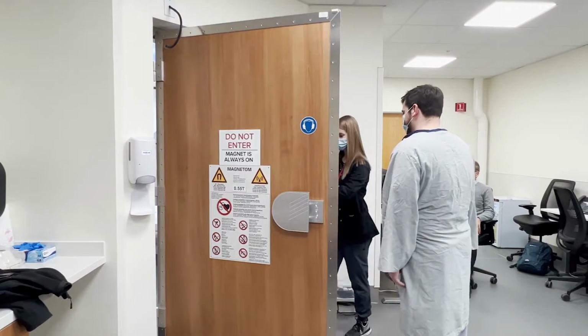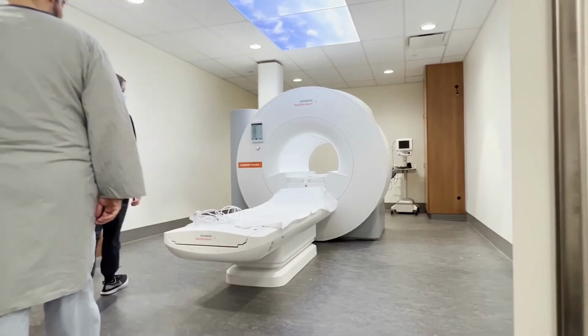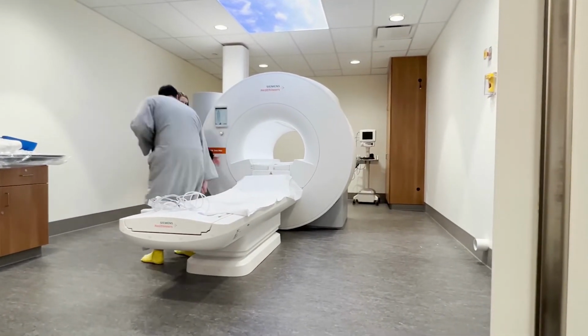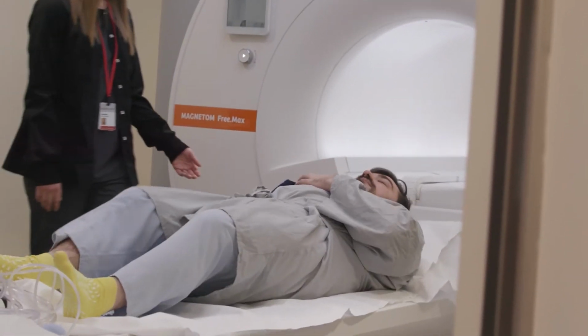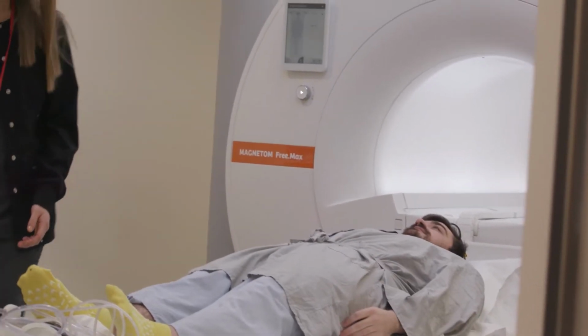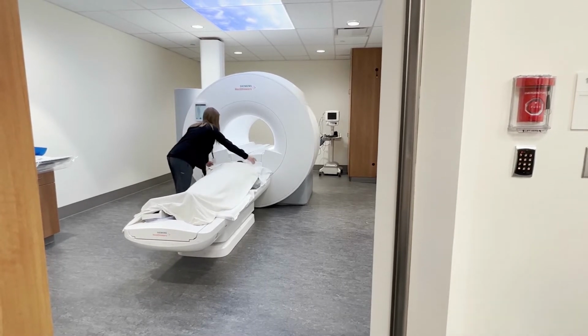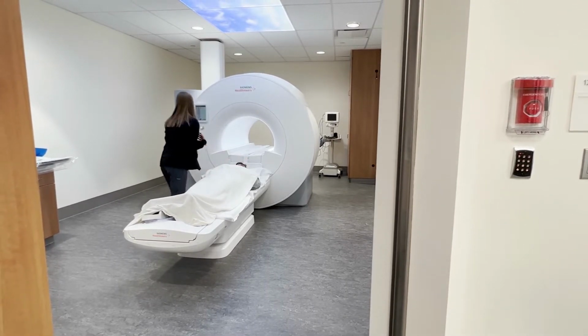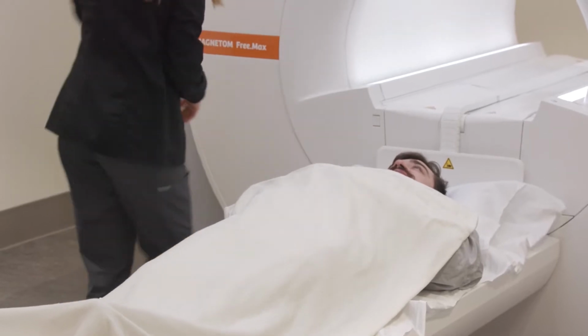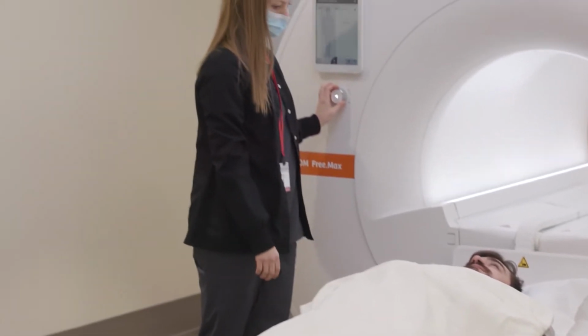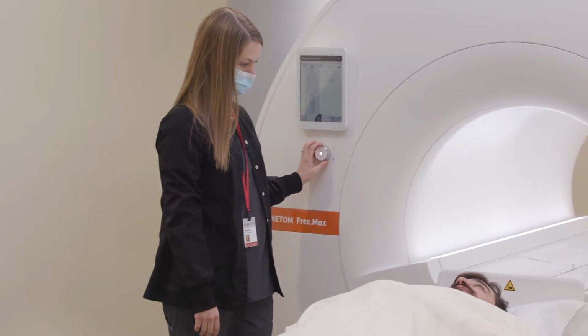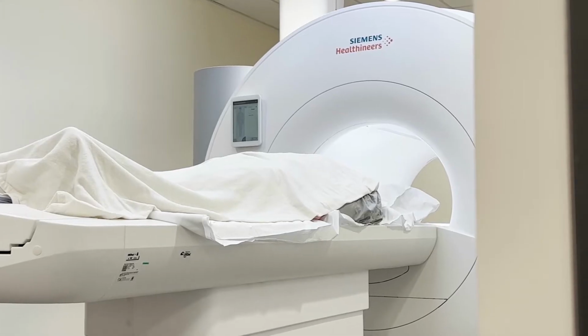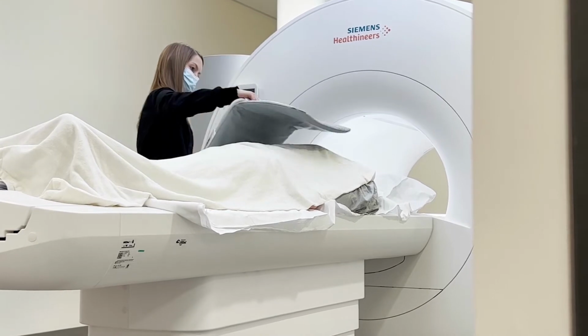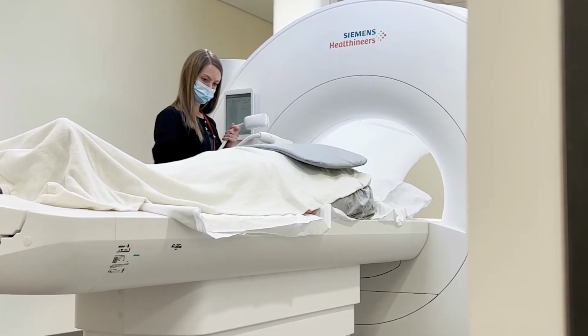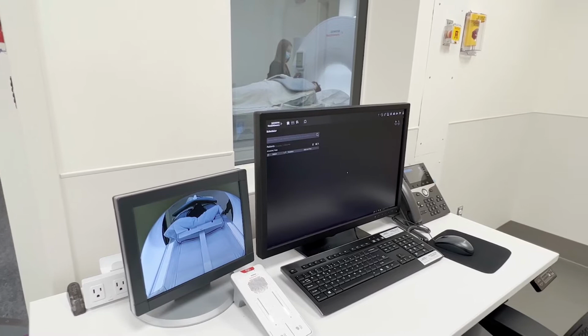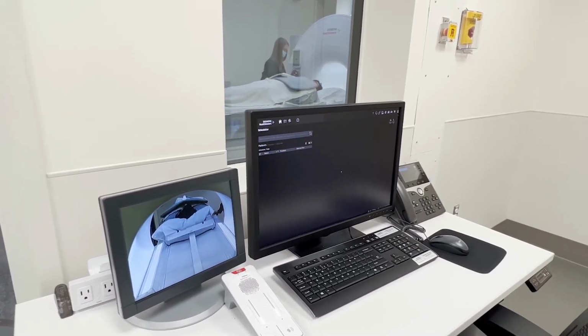I guess the primary disadvantage, if I want to start with that, is that the lower the magnetic field strength, the less MRI signal is available to form our images, right? So that's why there's been a push towards higher field. But low field brings a number of advantages. One is just the cost. The size and weight of the machine are all reduced. The lower the magnetic field strength, the less expensive the system, the less expensive it is to install, and the magnet configuration can be more flexible at lower field.